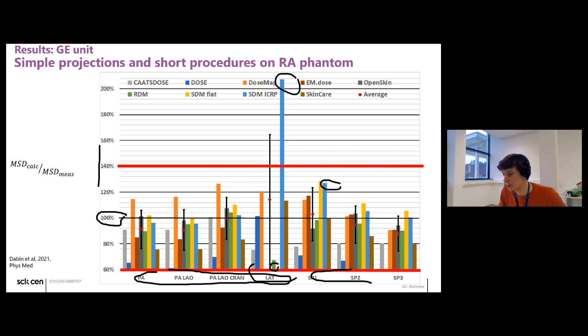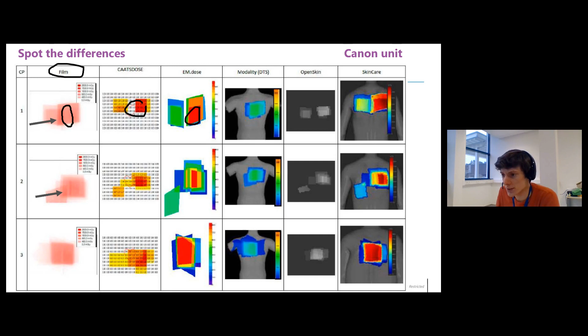And of course, that was just for the maximum skin dose. Most software tools also produced a skin dose map. And here you have the measurements with Gafchromic films, and then other columns represent the skin dose distributions. That was for a Canon system. And you can see that, in general, it looks good. The shape and the position are rather well respected, although for the first two short procedures, you can see that the maximum skin dose is at the intersection of several fields, and that's not always well represented in practice.